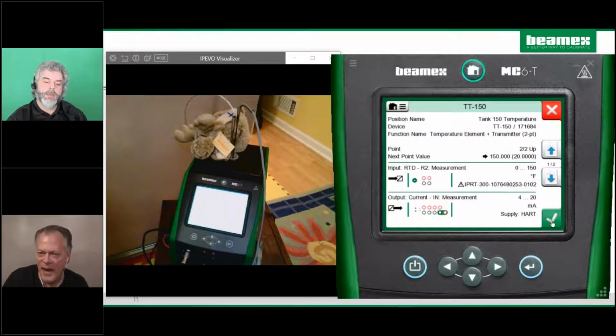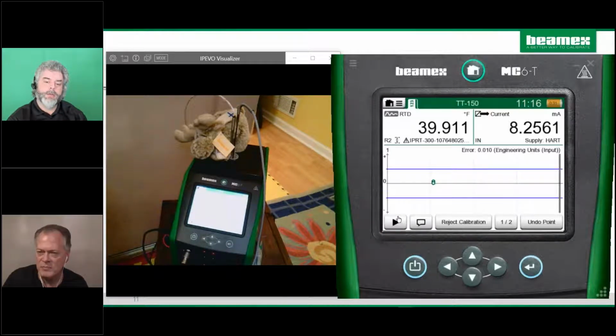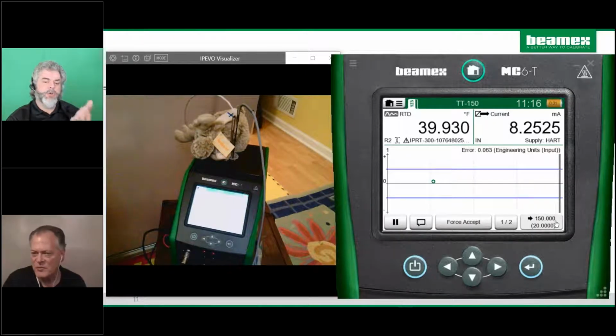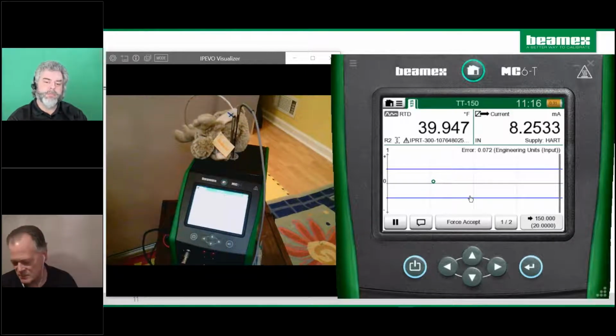Now we're going to flip back to the probe, and now the set point is 150. So how do you know that the set point is 150? It's right down here, and the expected milliamps at 150 is going to be 20. So this is our target, and this gray line is the scale. You can see this is 0 to 150 over the range, and our first test point occurred here around 40 degrees.